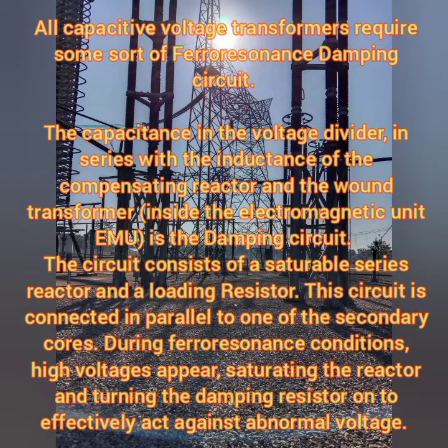The circuit consists of a saturable series reactor and a loading resistor. This circuit is connected in parallel to one of the secondary cores. During a ferroresonance condition, high voltage appears, saturating the reactor and turning the damping resistors into an effective act against the abnormal voltage. Just for understanding, we will learn more about the ferroresonance condition.